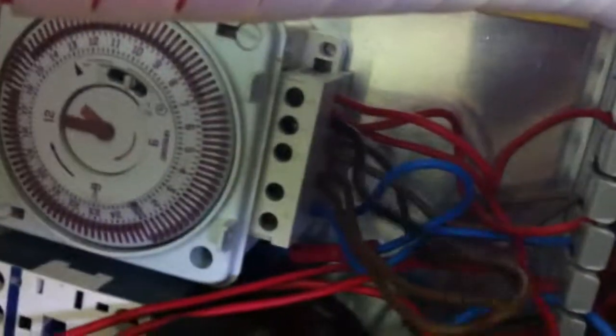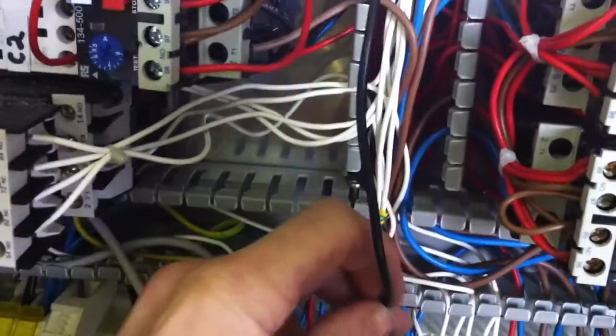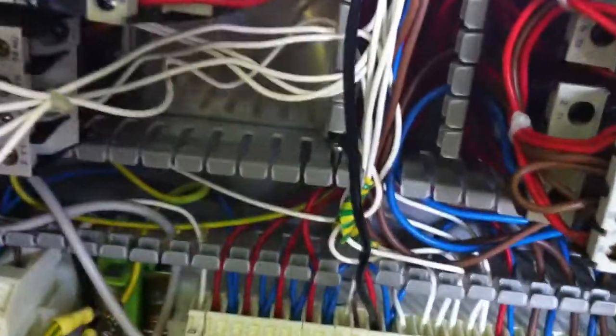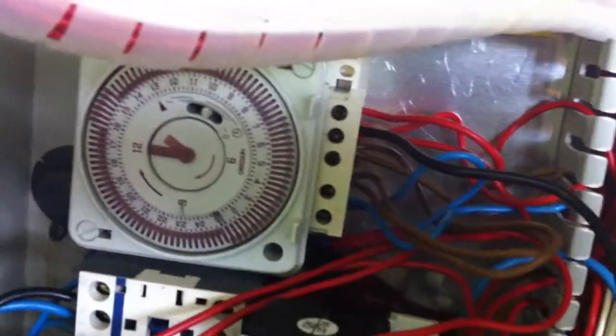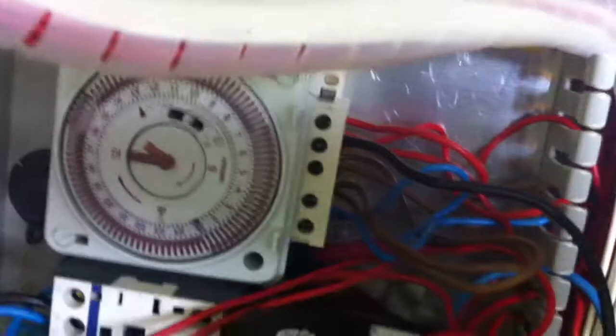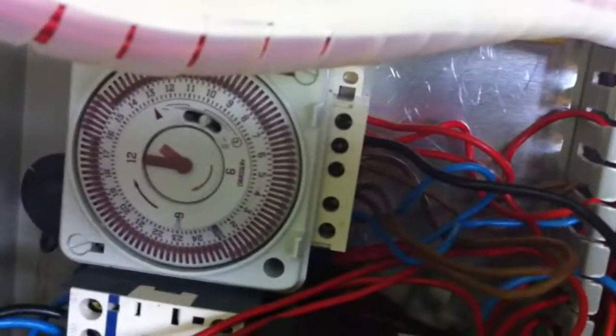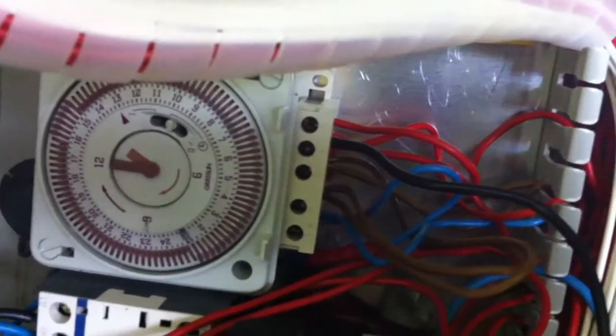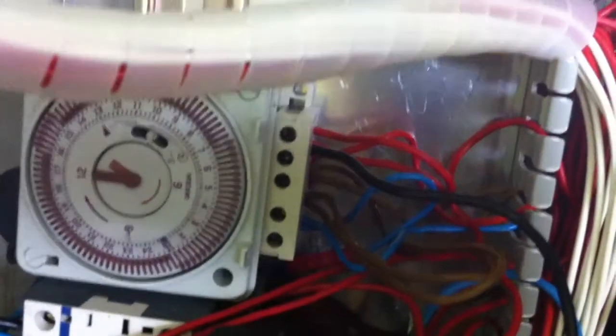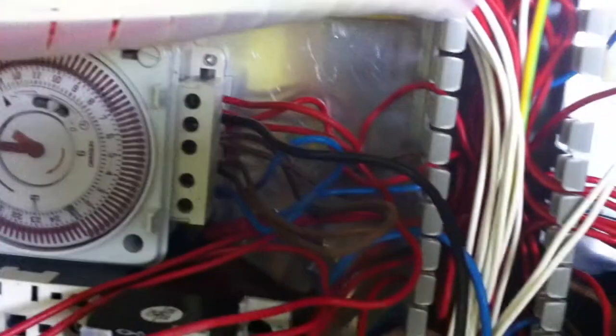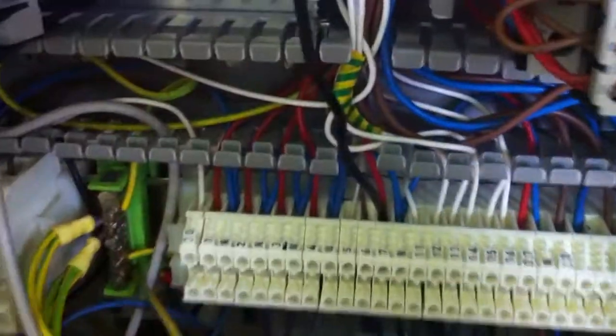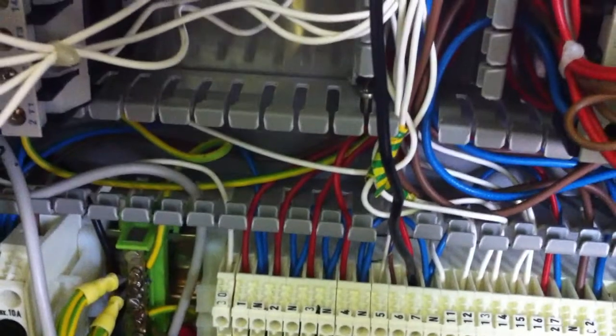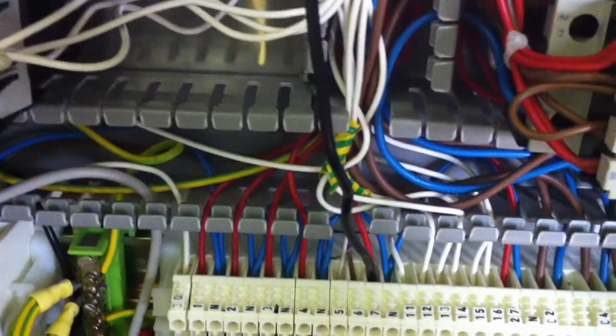The black wire has been tapped into the time clock. So I think that somebody's set it up so when the time clock is on, it runs purely off the clock. There's no ice bank control on it at all. So we'll remove this and see what happens.